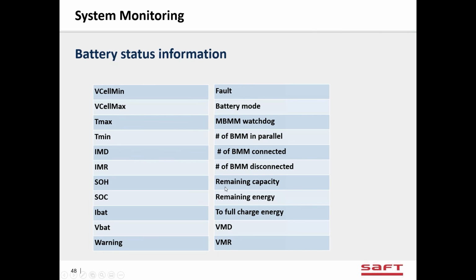This is some of the information that's displayed on the screen. A lot of these are acronyms that don't make a lot of sense, but you can kind of get the sense for maximum cell voltages, maximum temperatures, states of charge, battery current, battery voltages, warnings and faults. If you have a system with 4 strings and one of the strings is disconnected, it'll tell you, and then you can get this information. So these are the types of things that you can read both on the screen and remotely by the communication protocols.